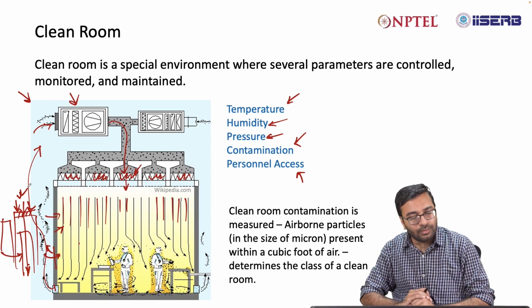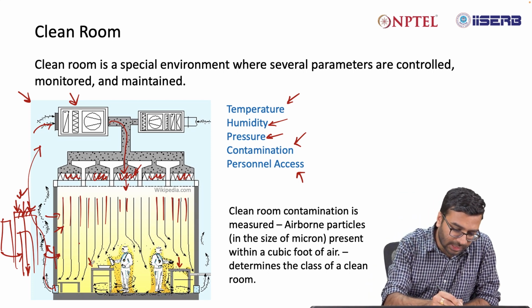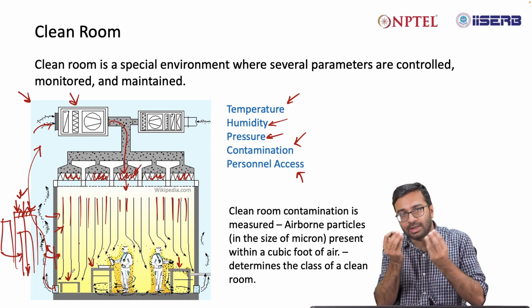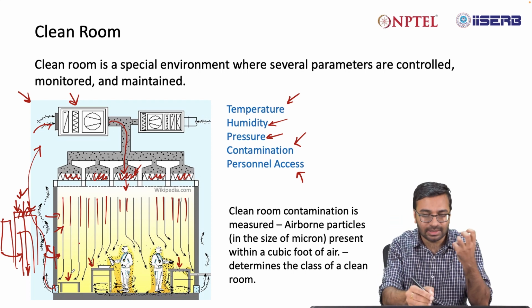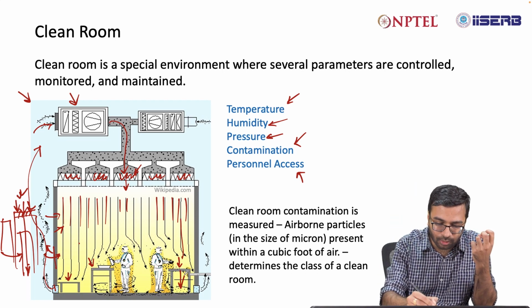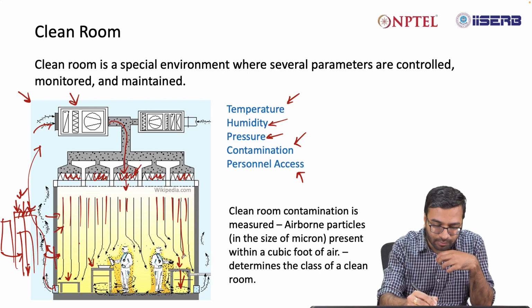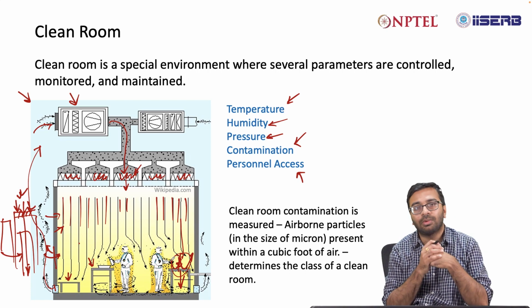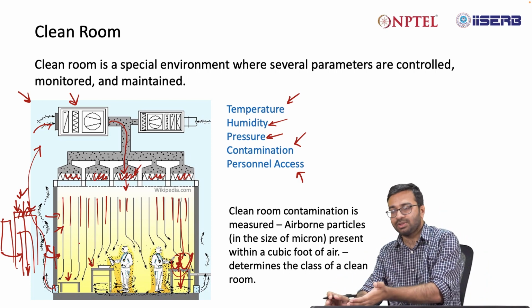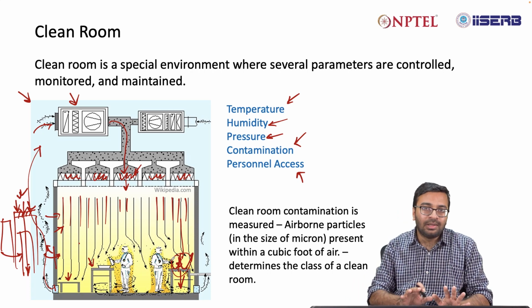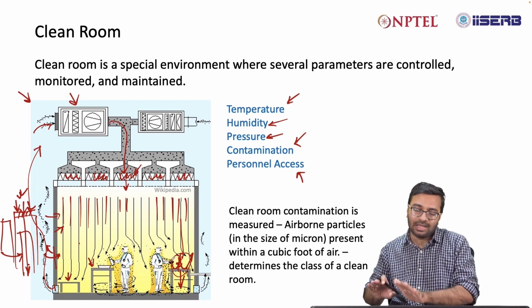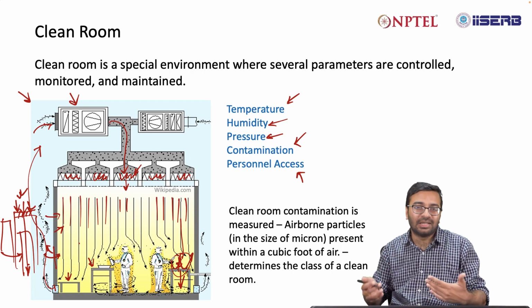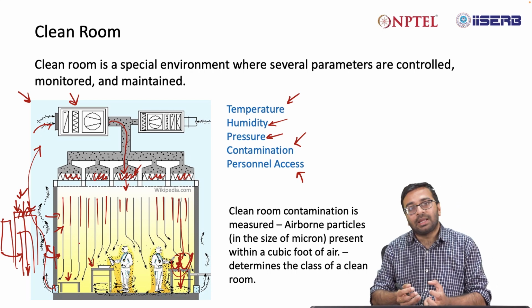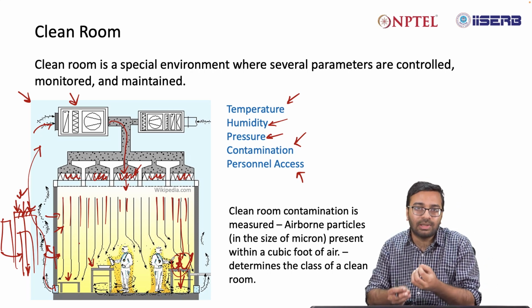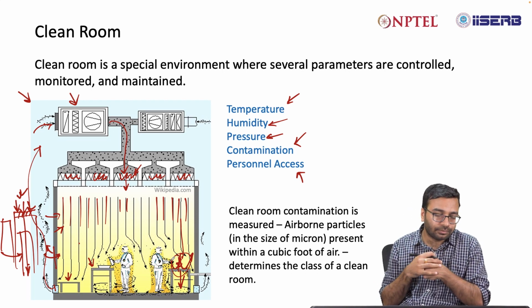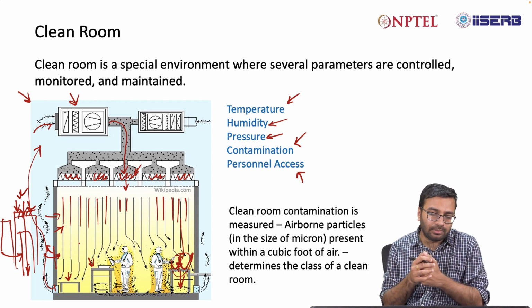And if you look at the tables used in a clean room, there are small holes on the surface of the table, so that the air coming from the top gets a way to go below the table. Otherwise it will reflect from the surface, and there will be more turbulence on top of the table. Most of the devices you will keep on the table only. So if there is turbulence around, then even dust that has deposited on the table can again create issues. So it's better to make an arrangement through which the air can pass through the table. That's why they make small holes on the table, or chairs, in most of the furniture.